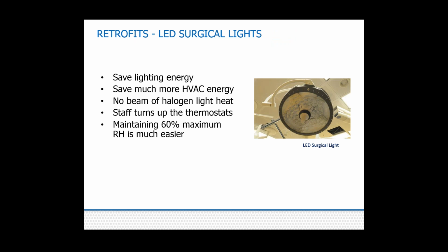So I'm just going to finish up with an item about surgical procedure lights. And at first you may think, well, what's this got to do with ventilation reset? Well, what we have found is that the traditional surgery lights are basically an incandescent style of fixture, a halogen, which is somewhat more efficient, but it still puts out the bulk of its energy as a beam of infrared heat, which is heating up the people in the operating theater. And because of that, they want to turn the thermostats down.